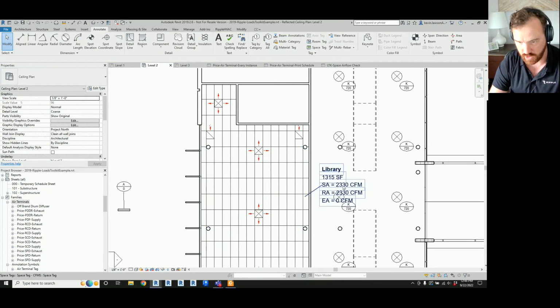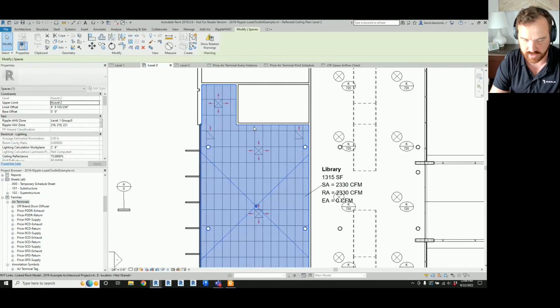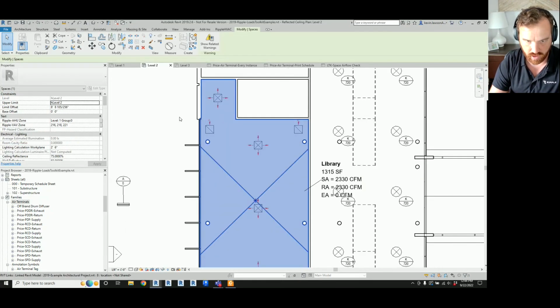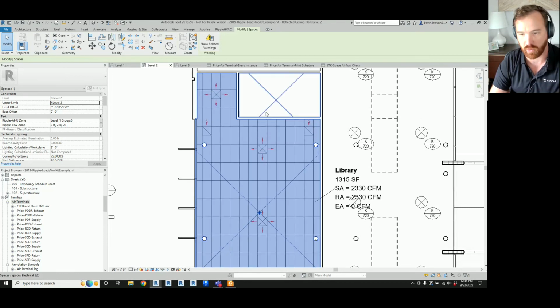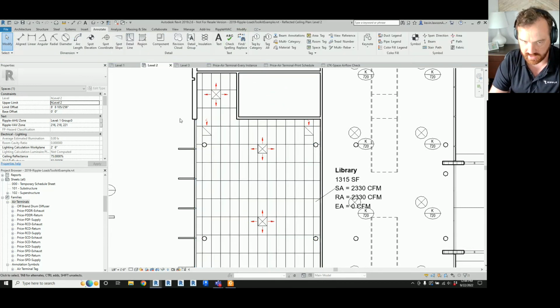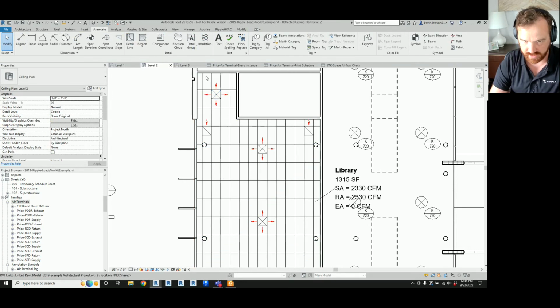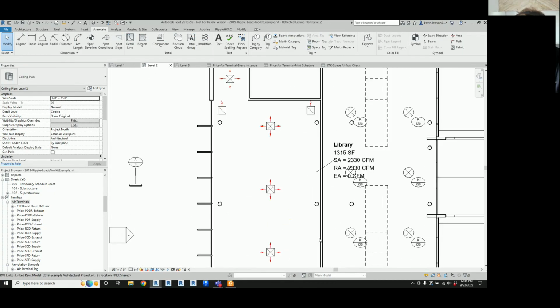So basically, the equation is 2330 CFM times this area over the total area. So you don't have to bring in separate CFM numbers. It automatically breaks down your NUCs. And that's how it works. But it just does it in proportion to the area, which is another good thing to keep in mind. If this is like a NUC full of hot plates, maybe you want to assign more CFM to this. So this assumes kind of consistent load across all of the spaces.